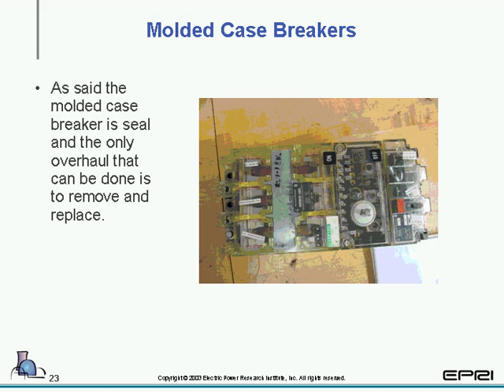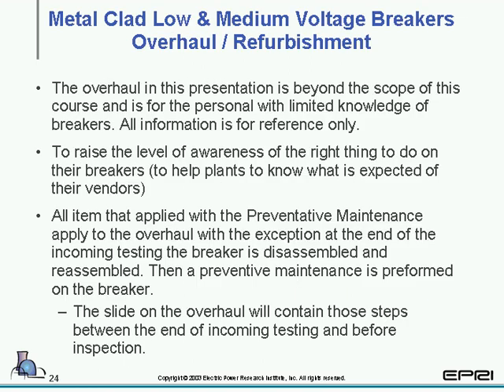As stated, basically with the molded case, or sealed or semi-sealed, there's no real overhaul that I'm aware of that is actually performed to a good degree. So we're going to be taking a look at low and medium voltage breaker overhaul. And again, this presentation is beyond the scope and course for anyone who's going to be performing the overhauls. It's basically a guide to, if you're having your breakers overhauled or you're planning to do your overhaul, items that you definitely want to consider and raise the awareness.